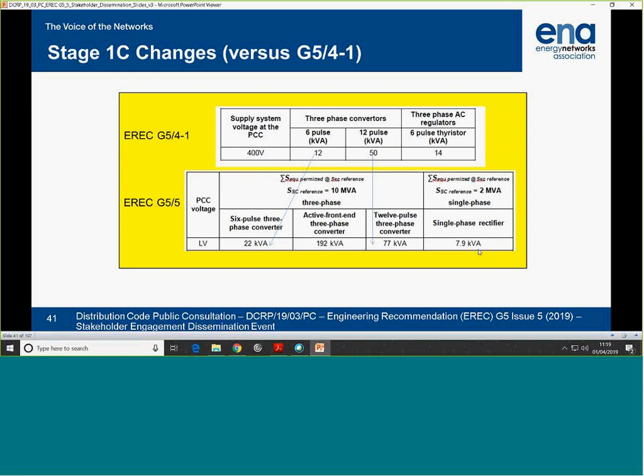The reference fault level for that is only 2 MVA. What it's saying is, if you have a fault level of 10 MVA, you can have 22 kVA. If you have a fault level of 20 MVA, you can have 44 kVA, and so on. What's not there is the thyristor. It was not thought we had enough of those going forward to warrant bringing it through. But if there are concerns in the consultation, then that can be resurrected. See how that goes.